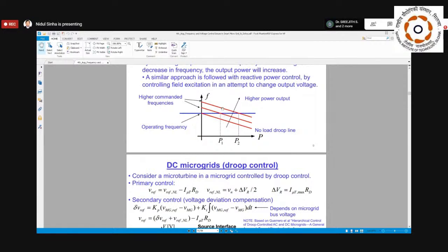In that case, the action of this primary control, or droop control, will be over in seconds to milliseconds time. Now the frequency system is left with less than 50 hertz frequency.